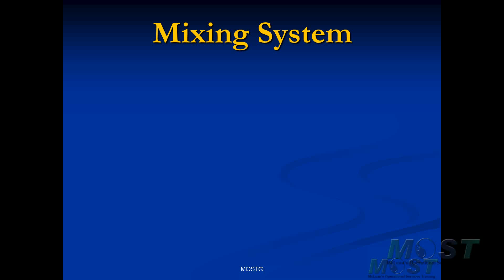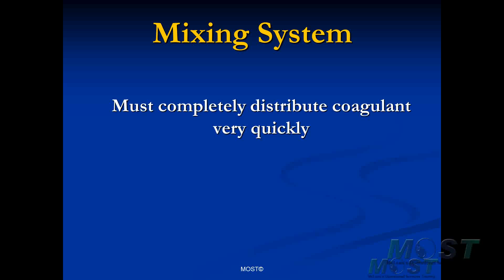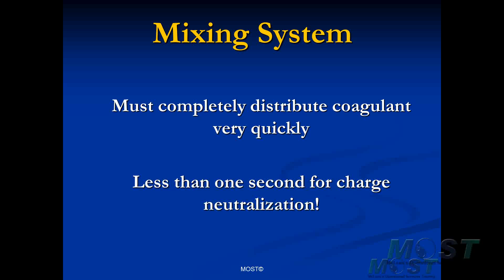The mixing system has the responsibility of distributing our chemical very quickly. In the case of charge neutralization, this has to be less than one second. So we have a significant mechanical challenge on our hands here to effectively distribute all of our primary coagulant within a one-second period and have our coagulant come into complete contact with all of the raw water entering our treatment plant.